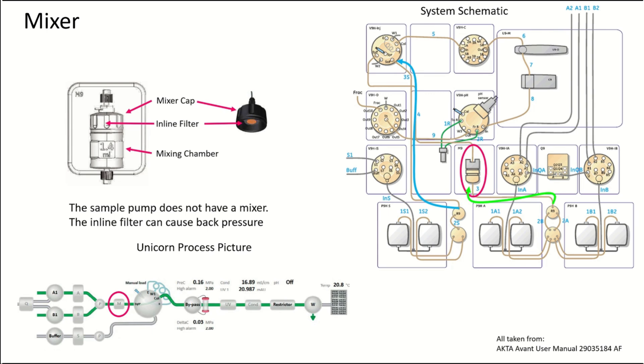It's also important to remember that the system pump has the mixer. If you're loading your sample through the system pump, you're gonna end up getting some band broadening because of the volume of the mixing chamber. The sample pump just bypasses it.